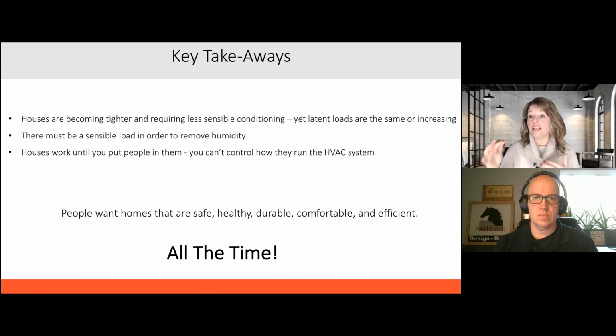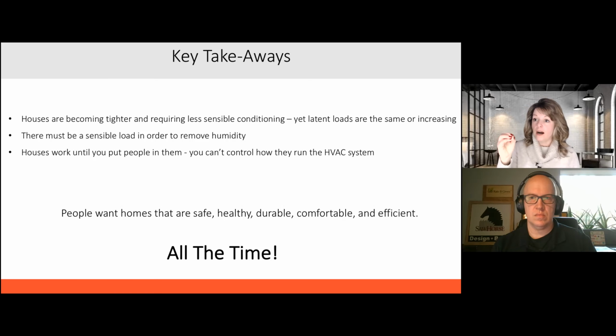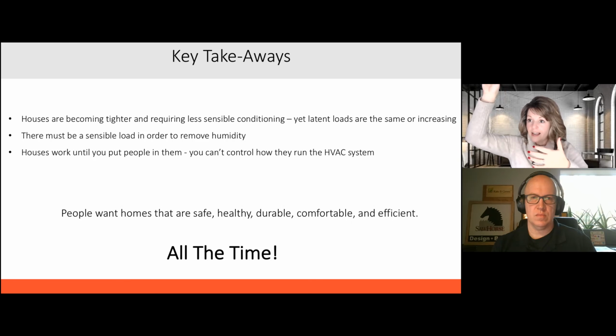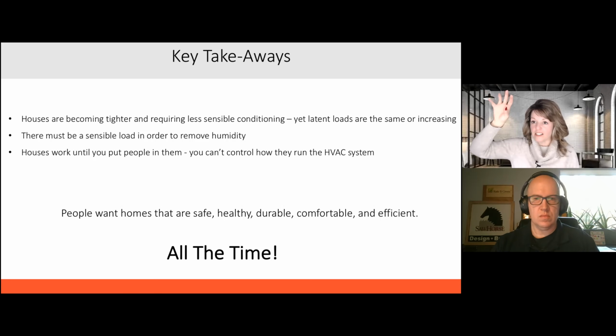Bath fan, you know, if you live in a humid climate, you should not be using a bath fan that is running off an RH sensor. Because if you do, what's going to happen is a vicious cycle in the humid months, where it's humid in the bathroom. So the ventilation fan's going to come on and it's going to suck in air through the house to try to make up for that exhaust, and it's going to suck in humid air, and it's just a vicious cycle. That humidity sensor is just going to keep that fan going and going. So if you have one of those, some of them come with a sensitivity option, meaning the RH is high, I'm going to come on and then run for 20 minutes or something like that, or just a pure timer.